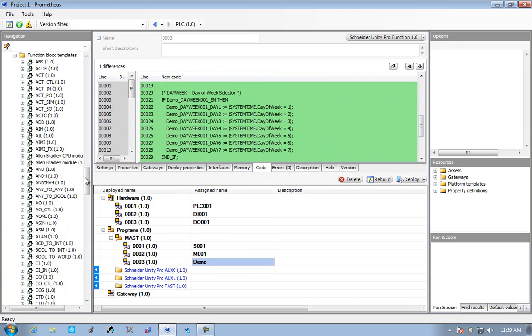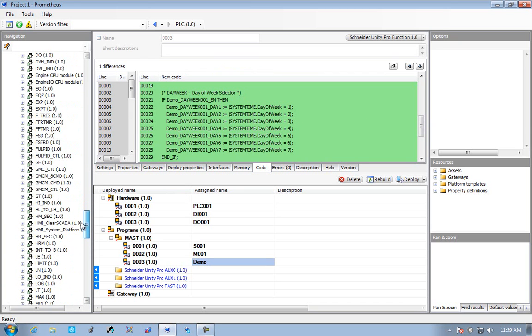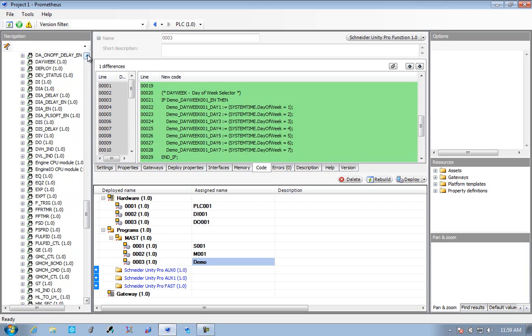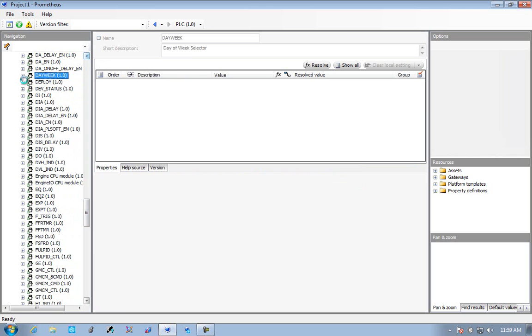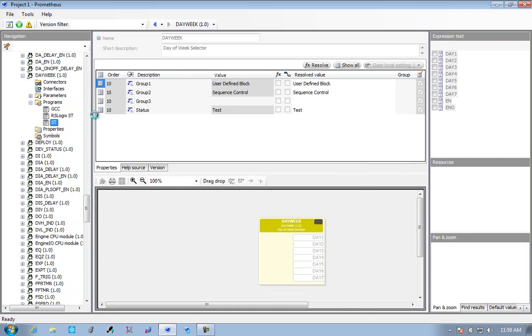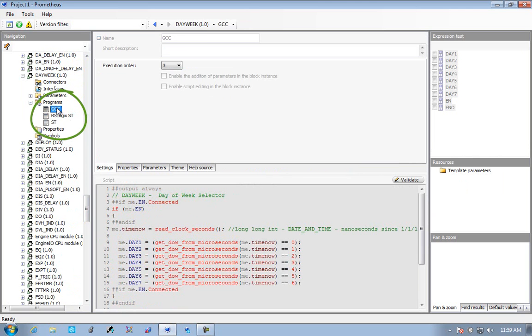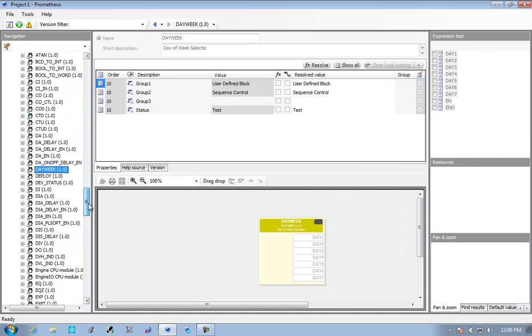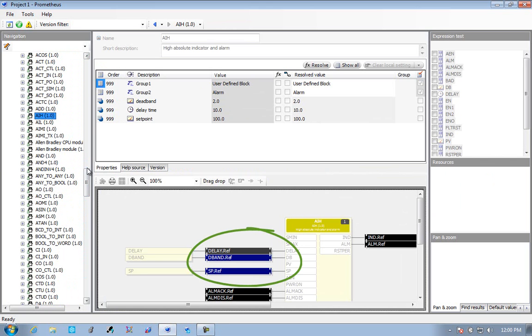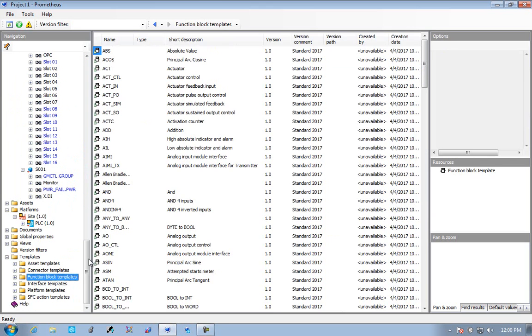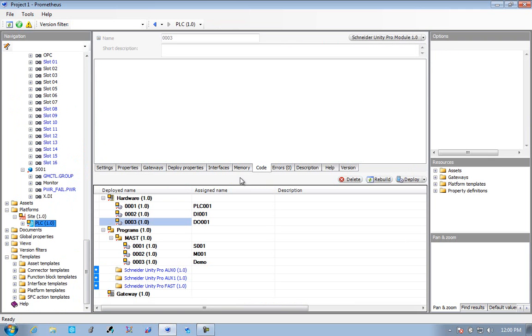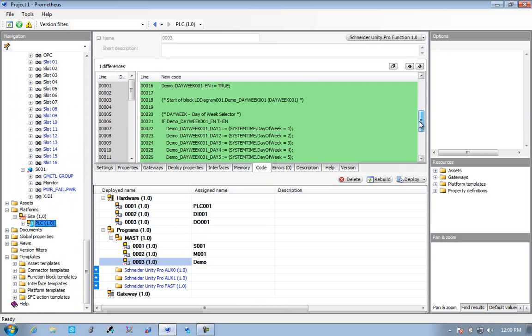Where did that come from? Because this is one of the important parts, is how do we get at the more detailed stuff that a processor can do, and how can we create usable functions? If we look inside, we'll see that there's a declaration for, in structured text, for getting time. We'll also see it's declared for three platforms. Each platform is declared individually. You'll also see that we can put HMI pins on our function block as well, so that when we drop a block in, it can come pre-canned with the entire HMI configuration along with the block. This also improves reuse greatly.